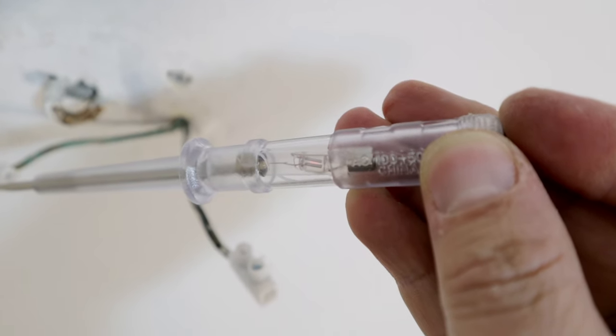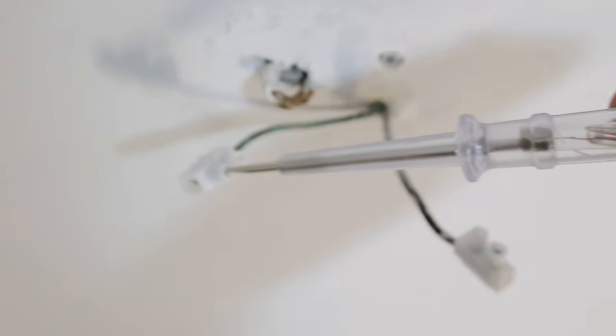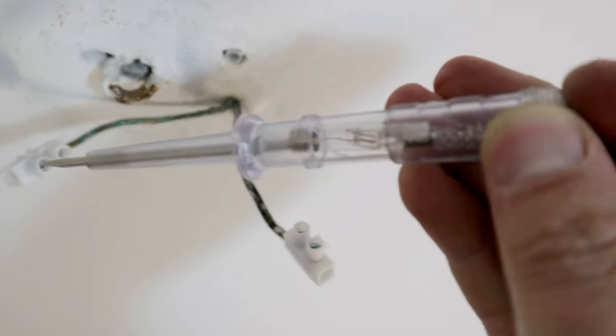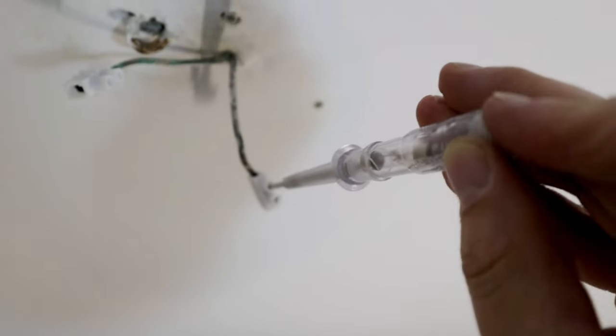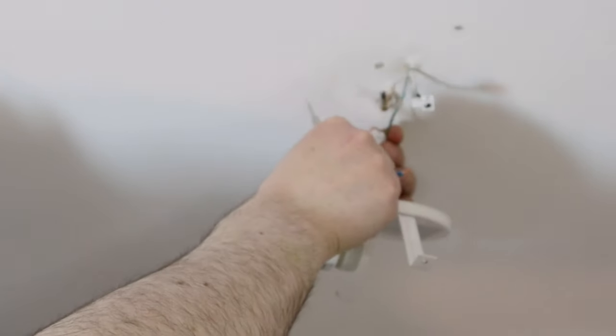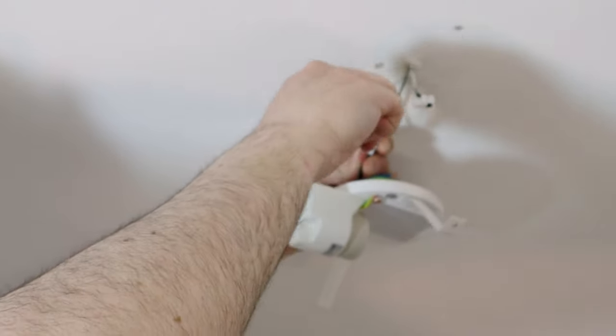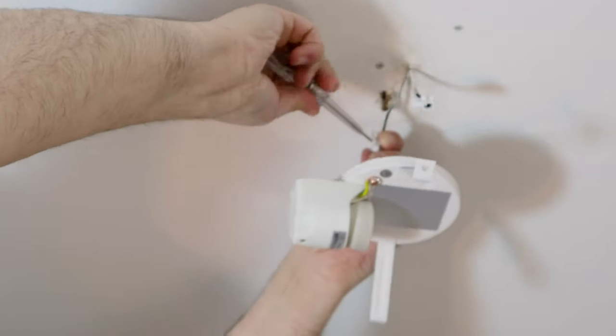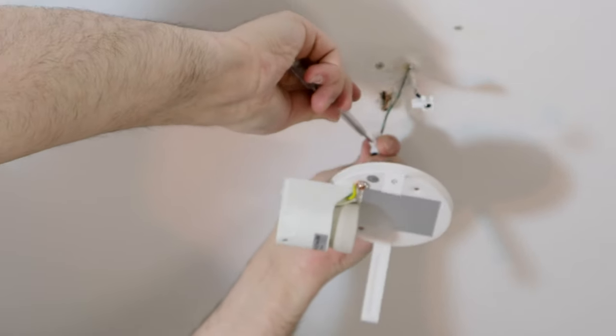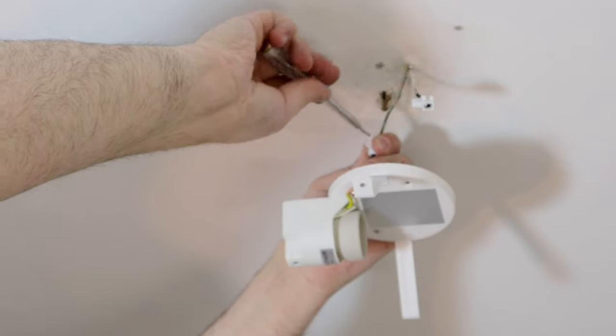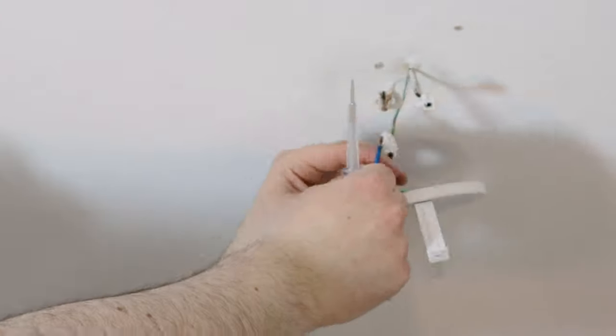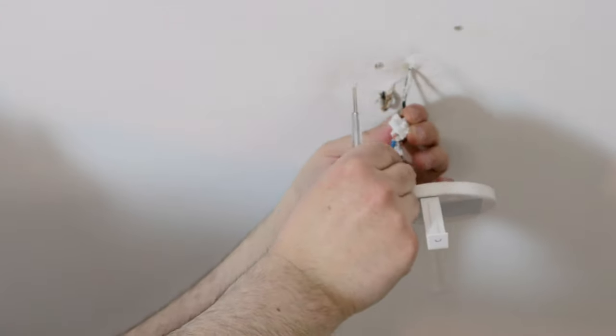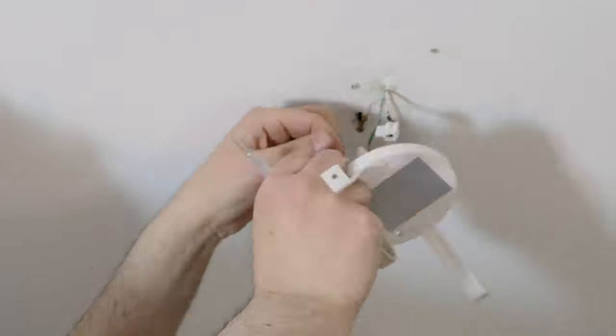Using a phase finder screwdriver, check which phase cable is and whether it is controlled by the switch. If it is the phase cable, the bulb inside the screwdriver lights up. I connect the ceiling light cables to the wire connectors of the respective ceiling cables. Before screwing, it is advisable that all the cables and connectors go inside the base of the ceiling light.